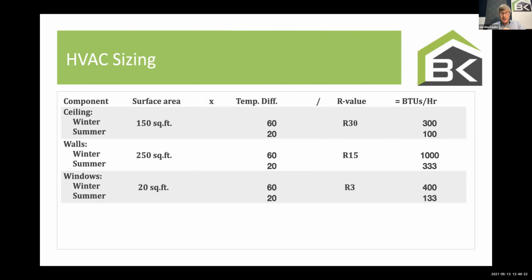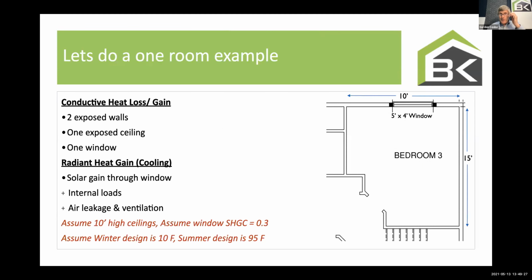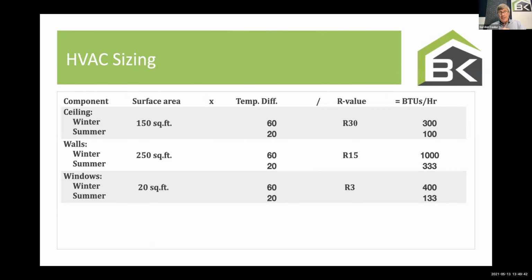You would take the surface area, both summer and winter, 150 square feet, and you're going to go back, wait a minute, that's not exactly 150 square feet. I don't know if you can see my cursor, but the entryway, but we don't quibble over that. Obviously, you should do a click, click, click and figure out the actual square footage, but for this purpose, I'm using 150 square feet. And the temperature difference, remember, is 70 in and 10 out, a temperature difference of 60 degrees. In the summertime, the temperature difference is 95 to 75, so 20 degrees. And in both cases, I divide it by 30. And you'll notice, it's 300 BTUs of heat loss, and it's 100 BTUs of heat gain. Not a lot of heat gain. And you go, yeah, but the temperature in the attic's double that. Sure.